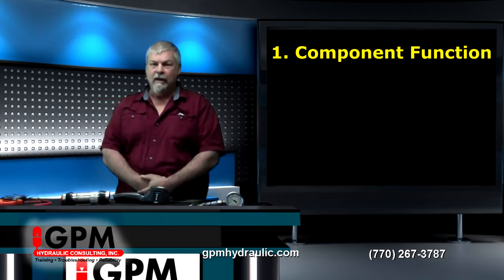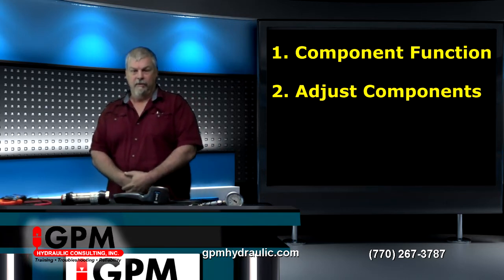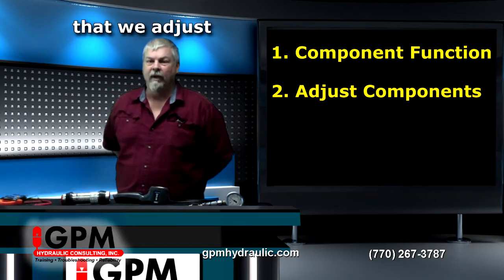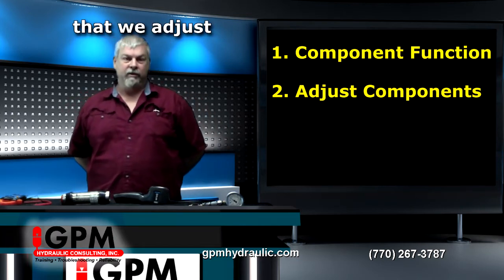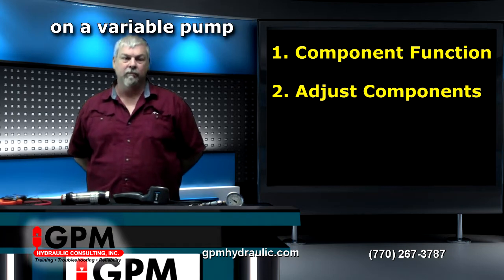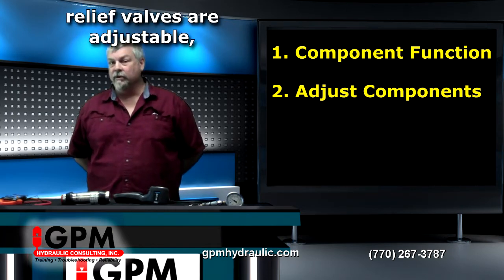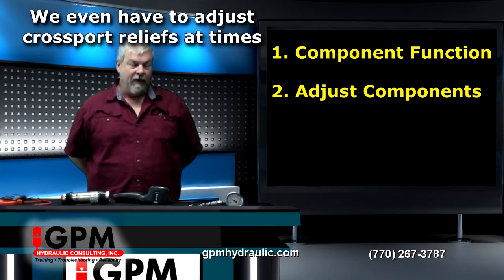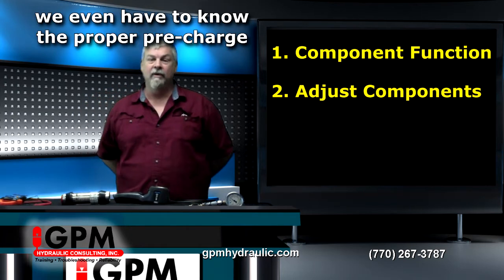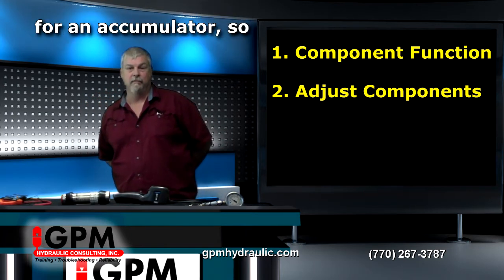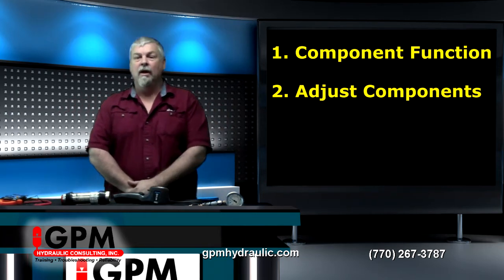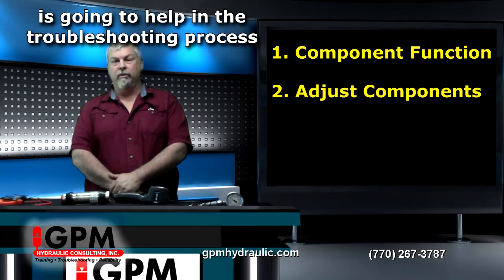Another thing is how to adjust a component. There are many components in the hydraulic system that we adjust. The pump compensator on a variable pump is one. Relief valves are adjustable. We even have to adjust cross-port reliefs at times, and we need to know the proper pre-charge for accumulators. Knowing how to adjust these components is also going to help in the troubleshooting process.